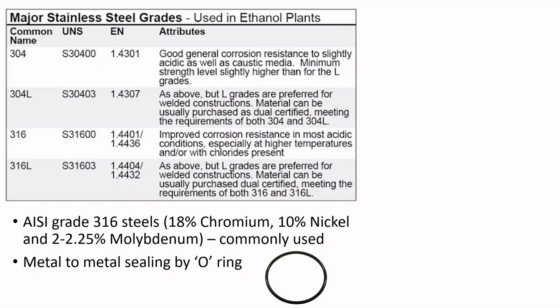The most commonly used stainless steel in bioprocess industry is 316 and 316L, which have high resistance to acids, alkalis, and halogens. The composition of 316L steel is 18% chromium, 10% nickel, and 2–2.25% molybdenum. When stainless steel sections are joined, an O-ring seal is used at the joints — similar to the O-ring seen in pressure cookers or autoclaves — to seal the stainless steel fermenter. That concludes the discussion on the body of the fermenter.